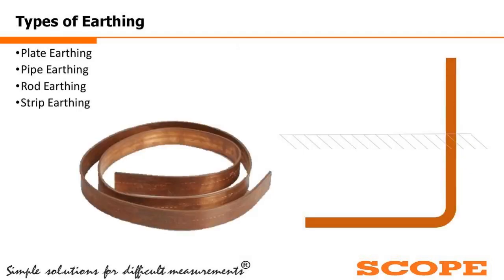Then comes the strip earthing. Its use is very limited, in very rare conditions. Strip earthing can be considered a way to increase the surface area of the earth plate, because if it is a rod, it might not be possible in some terrain, such as rocky terrain, where digging a deep pit might not be possible. In such a very special case, people use strip earthing, where a copper strip is laid horizontally, as shown on the right-hand side.